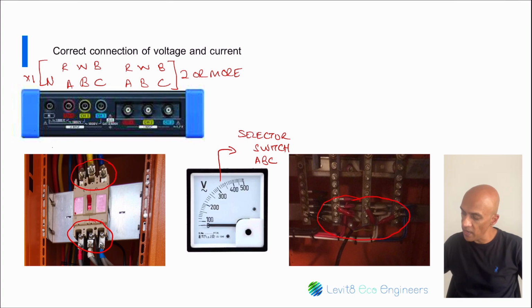So here you see we have the bus bars coming out of the circuit breaker, and they've got a little bolt and nut connection for all the outgoing feeders or all the outgoing circuits, and you could connect onto that. Now, we will talk about safety later when we get to the actual connections and measurements, as it is one of the most important aspects of conducting a successful measurement.